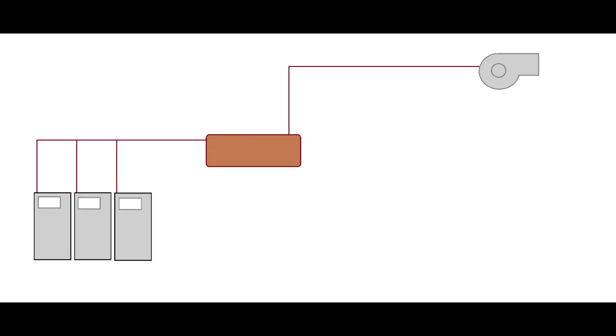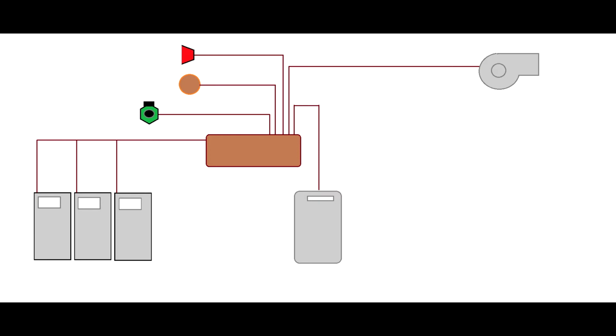So after I designed the boilers, my manager decided to deal with the company which integrated the boilers into an entire heating control system. So they fitted a building management control, a Compri HX in my case. Now, when we go to gas courses, we're told that if we have mechanical ventilation in the boiler room, we're supposed to have these fans, differential pressure switches, interlocked with the boilers. In my case, the boilers were interlocked with the building management control, but not in a safe way.